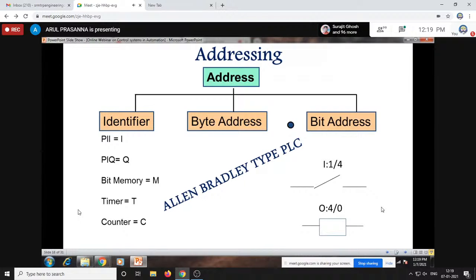Some notations and terms change depending upon the manufacturer. And as I said, addressing starts with the 0th byte and 0th bit, which is the universal default for all types of PLCs. Even with Allen-Bradley, it will start with I colon 0/0. From that we can start our initial input address.